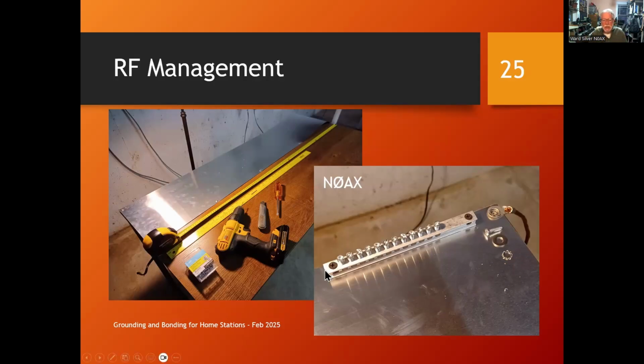And then for the connection, instead of that copper pipe, I went and bought a bunch of these ground bars that go into the AC service panels. If you open up your service panel and take off the cover so you can look at all the wires coming in, you will see these kinds of things on each side of the panel. And they're made to do exactly what we want. They have a nice big heavy screw. They have a hole for you to put the wires in, and you can torque those suckers down and it will be tight. Okay, and so you just bolt this directly to the aluminum panel with a screw, and you put a tooth lock washer under every screw so that it bites in to the aluminum, both of the reference plane and of the grounding bar. Use tooth lock washers whenever you can.